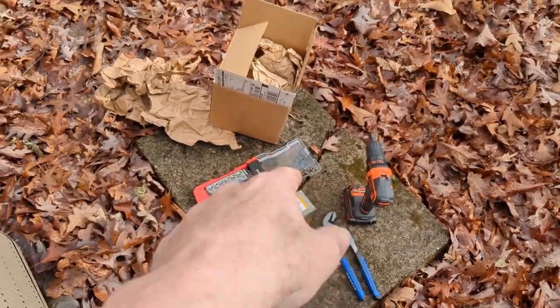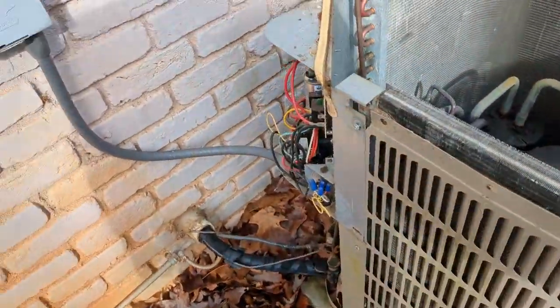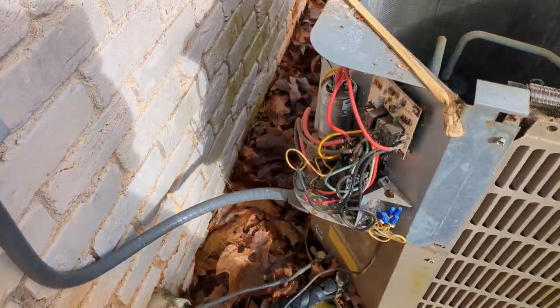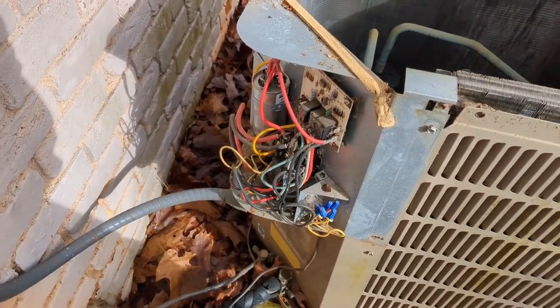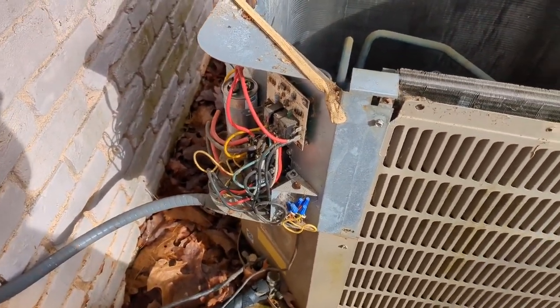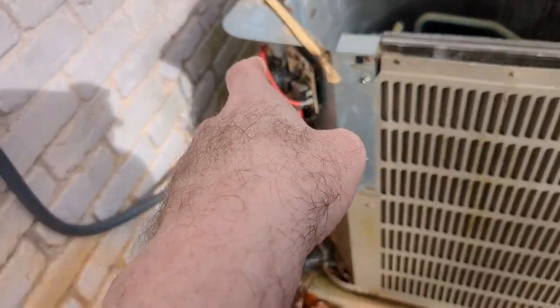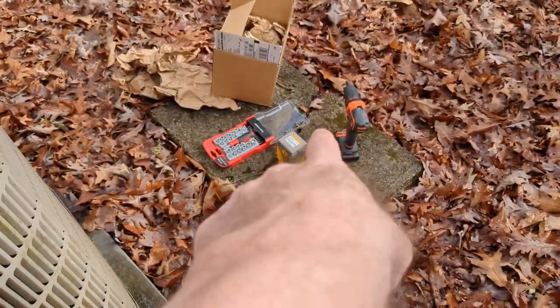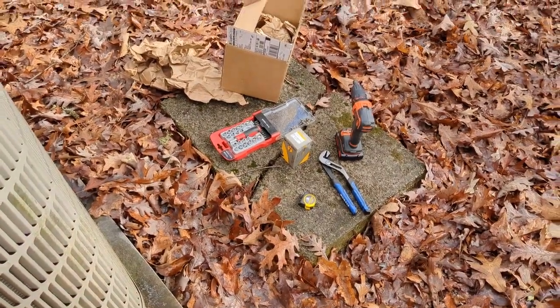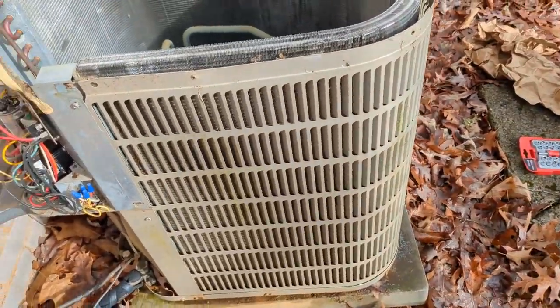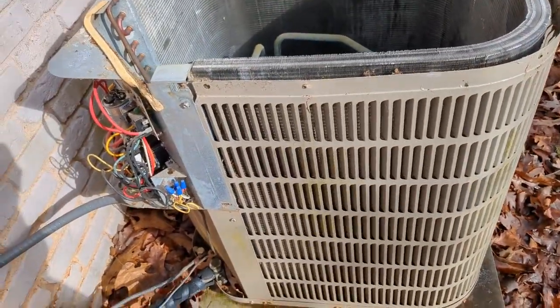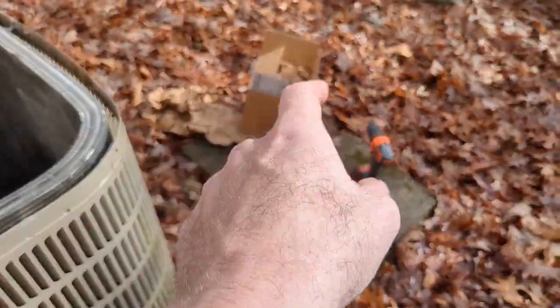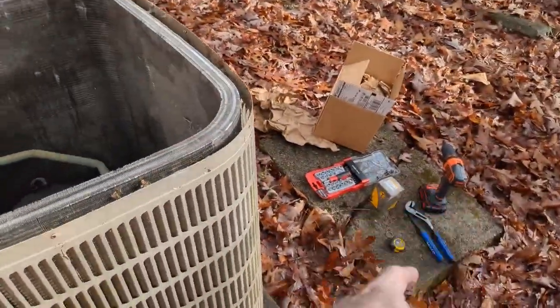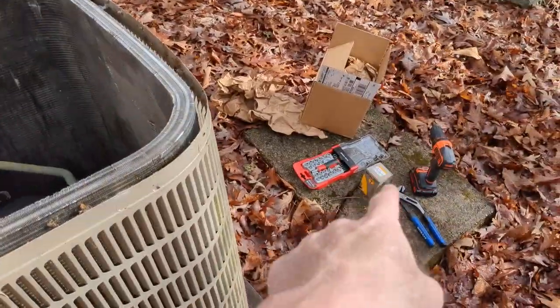So there's the new one. Although, to be honest, that's a jarred one. It's not terrible. I'll check it with my capacitor checker and make sure it's still good, because if that cap is still reading within spec, I'm inclined to leave it alone and keep that one on hand as a spare. Because the last thing you want is, it's July, 95 degrees outside, and that cap blows and you don't have one on hand. So I might leave that one off to the side.